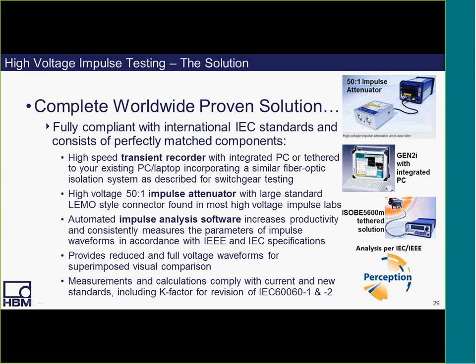The automated impulse analysis software increases productivity and consistently measures the parameters of impulse waveforms in accordance with the IEEE and IEC specifications. And we'll talk more about that in just a moment. But essentially what it does is provide reduced and full voltage waveforms for visual comparison.